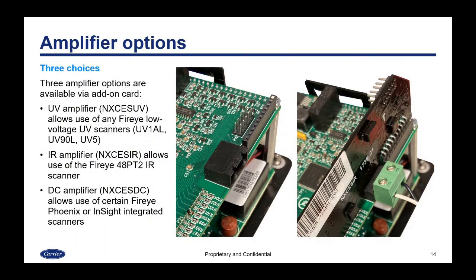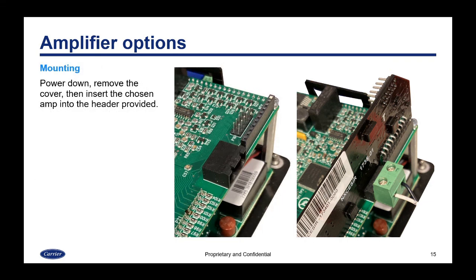You have 3 choices for amplifier options with the NXF4000, and those are fitted with an add-on card. The first is a UV amplifier, and that allows use of any Fireye low-voltage UV scanner. We'll go over that in upcoming slides. Then there's an IR amplifier and a DC amplifier, and that means direct coupled, and that allows use of certain Fireye integrated scanners. To mount the amplifier card, you're going to power down, remove the plastic cover, and then insert the amplifier card into the header that's provided on the circuit board. Replace the cover and repower.